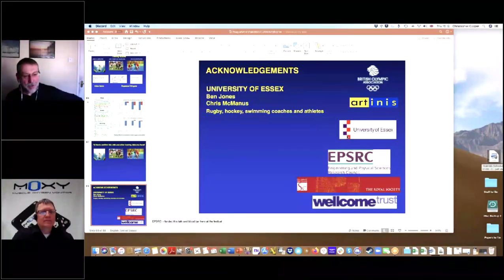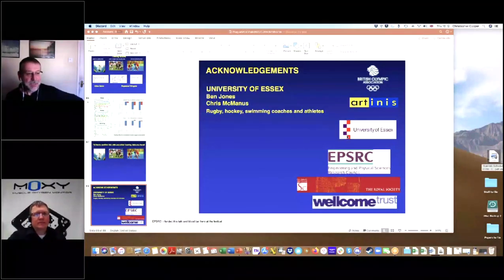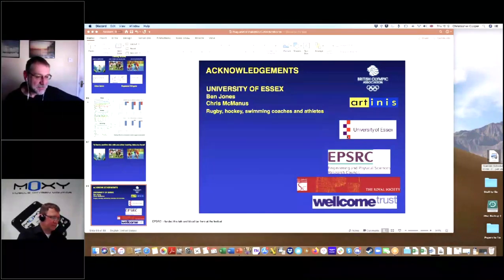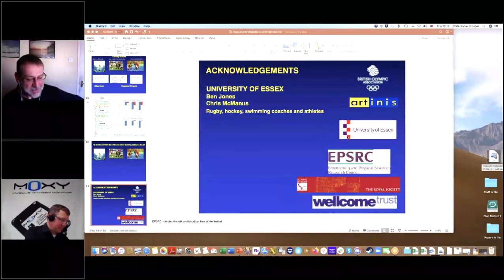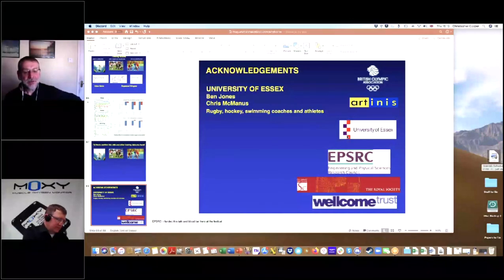So you get it by the Beer-Lambert law, and the modified Beer-Lambert law, where you need to allow for the path length. Now, if you measure the path length, that's great. You can assume a path length, and some studies assume an approximate path length. For the muscle, it's roughly 4 times the source-detector separation. On the MOXY, it's complicated because you've got model 2.5 and 1, so I won't use the MOXY as an example. But let's say the Portamon at 4 centimeters should be a 16 centimeter path length.